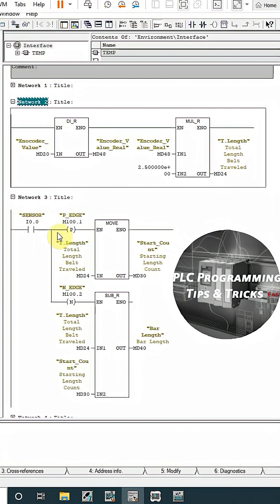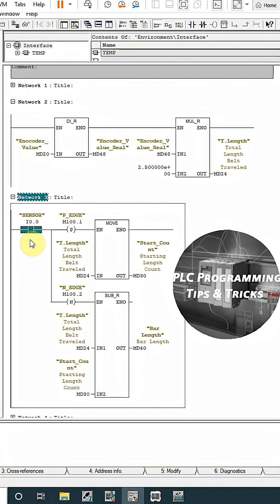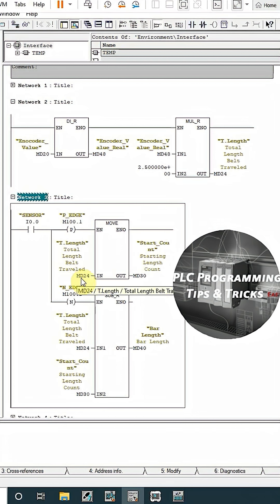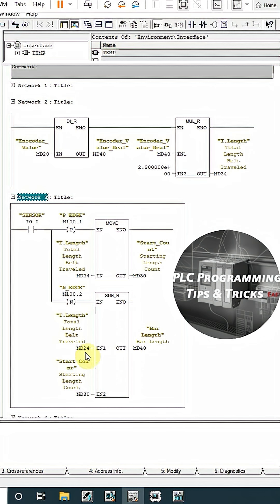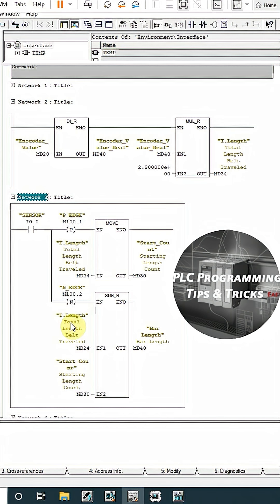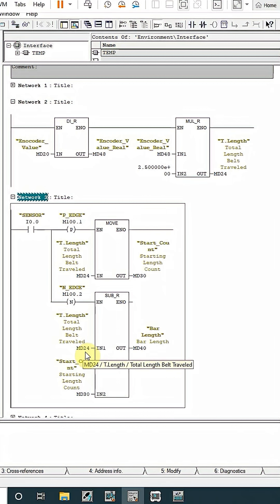In network number 3, now as the bar comes in front of the sensor at I0.0 on the rising edge, move this total belt length travel to the starting length which is MD30. So basically MD30 will take a load of total belt length travelled at the rising edge of the sensor. And as the bar leaves the sensor on the negative edge, we will minus this MD30 from the current or the total length travelled by the belt which is MD24.